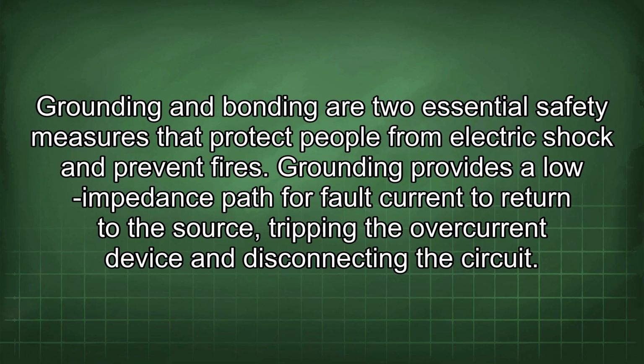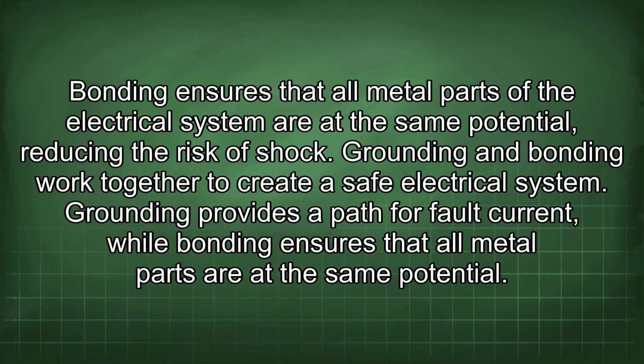Grounding provides a low-impedance path for fault current to return to the source, tripping the overcurrent device and disconnecting the circuit. Bonding ensures that all metal parts of the electrical system are at the same potential, reducing the risk of shock. Grounding and bonding work together to create a safe electrical system. Grounding provides a path for fault current, while bonding ensures that all metal parts are at the same potential.